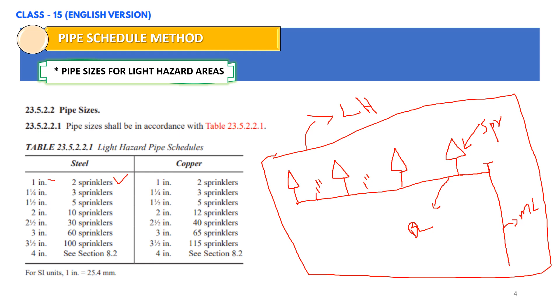So this will be one inch, and this also will be one-inch pipe. Here this will be the third sprinkler, so for three sprinklers, the pipe size shall be one and one-quarter inch. For two sprinklers: one inch; and for the third sprinkler, this pipe shall be one and one-quarter inch, or 32 mm. And up to five sprinklers, we need to consider 40 mm — that is one and a half inch pipe. Here we have only four sprinklers, so for the fourth and fifth sprinkler positions, we need to use 40 mm (one and a half inch) diameter.